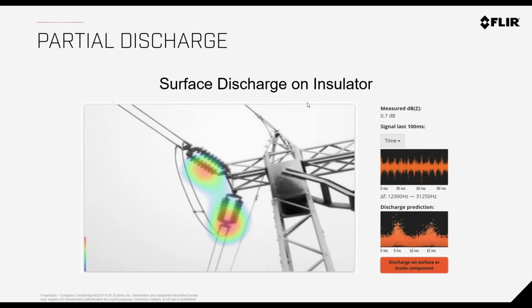Here's a surface discharge on an insulator, and judging by the ultrasonic spikes coming out of this, the artificial intelligence takes that information and tells you there's discharge on the surface or inside the component. When it's inside the component, those are definitely things you'll want to investigate, maybe get a cherry picker out and climb up to see what's going on.